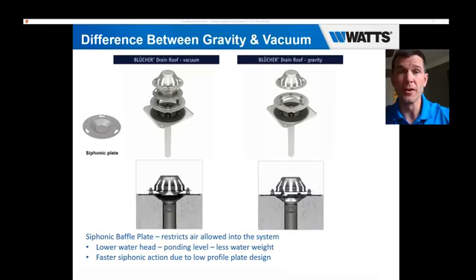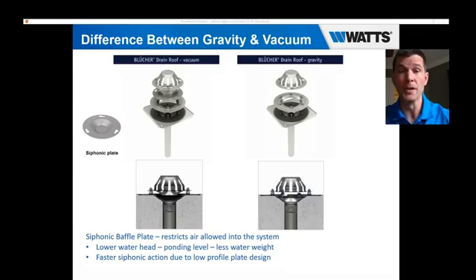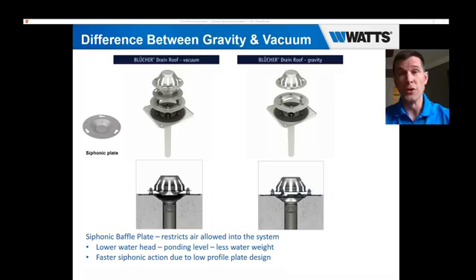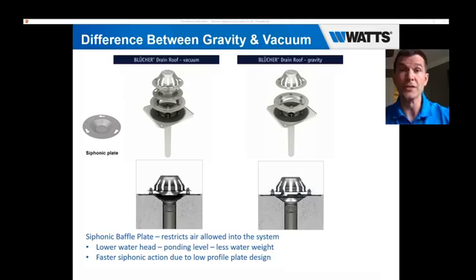One of the key differences from gravity to siphonic is what we call a siphonic plate or baffle. With both Blücher roof drain options, the drain itself is the same. This baffle attaches inside the top of the roof drain, right before where the water collects and goes down the vertical pipe. What that creates is a reduced potential for air to get drawn into the system and also decreases the amount of water ponding on the roof. As the water rises and goes past this plate, it closes off all of the air — and at that point, the siphonic action actually starts, drawing in more water.